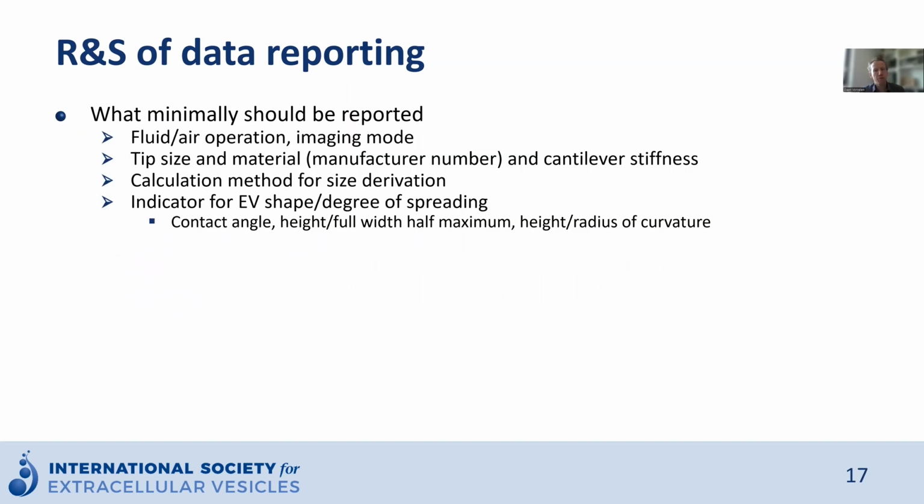Since AFM is still emerging as a tool for the study of EVs, general guidelines for what should be reported have not been really established. I would suggest the following. Always make clear whether you're operating in fluid or in air and which imaging mode you're using. Report your tip size and material, as well as the stiffness of the cantilever you've used. Also, provide the calculation method for the derivation of the size that you use, and provide an additional indicator for the shape of EVs, so the degree of spreading on the surface.